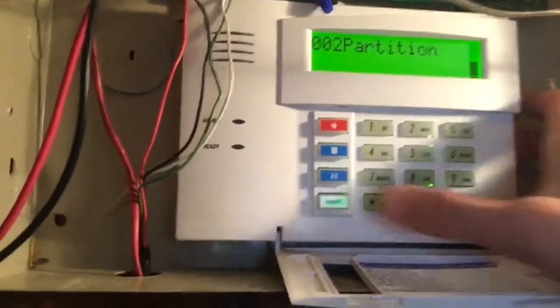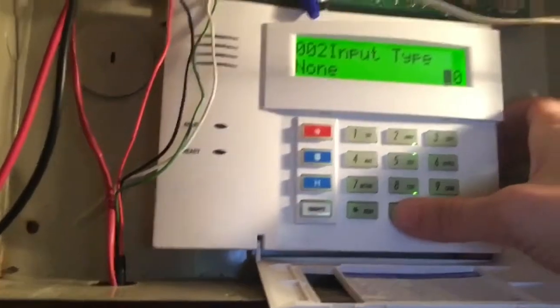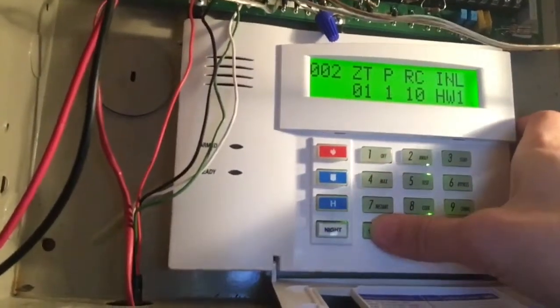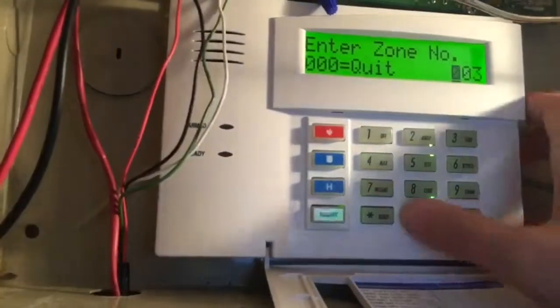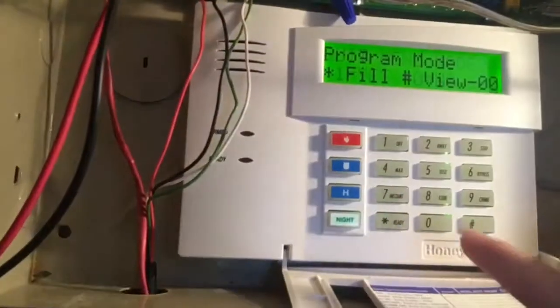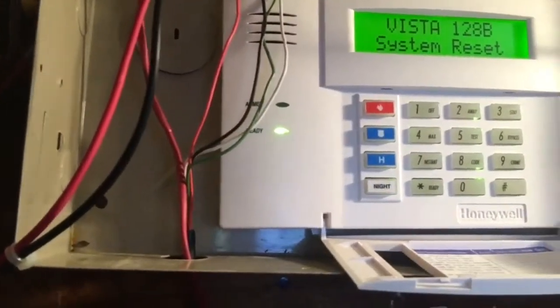Star to continue. Partition 1. Report code — we're just going to skip through that. Input type: this is a wired contact, so we are going to press 0-1 for hard wire. Star, then star again. It moves on to the next zone, so we can go ahead and get out of that — 0, 0, 0, star. Quit menu mode — yes. Star, 9, 9. Standby. Vista 128B system reset.